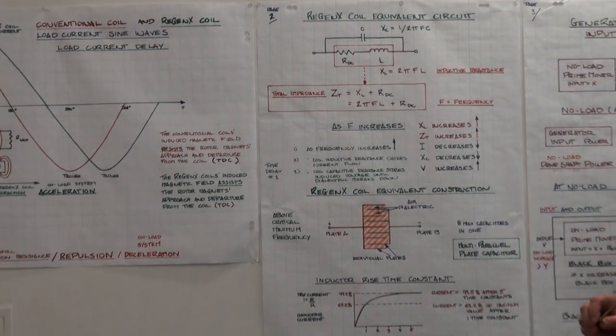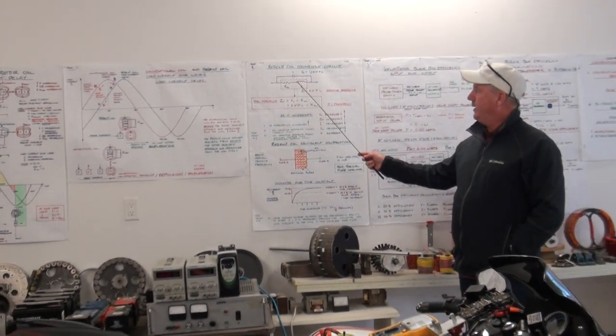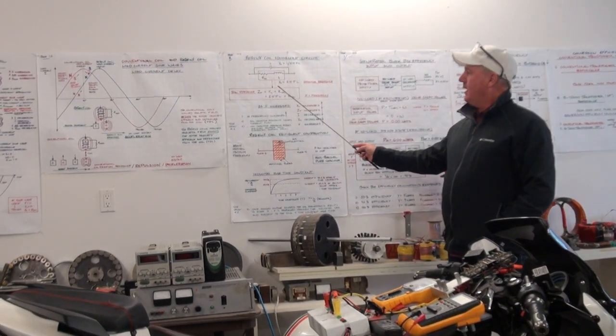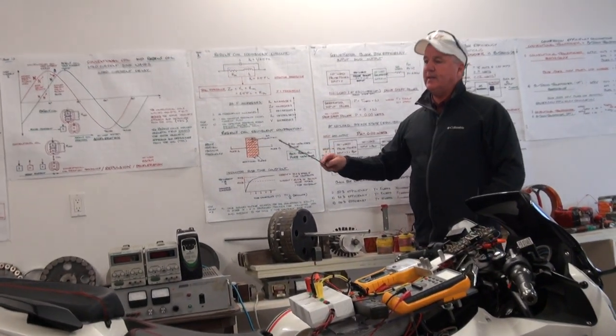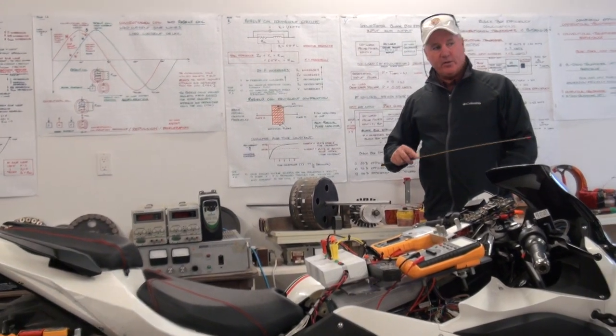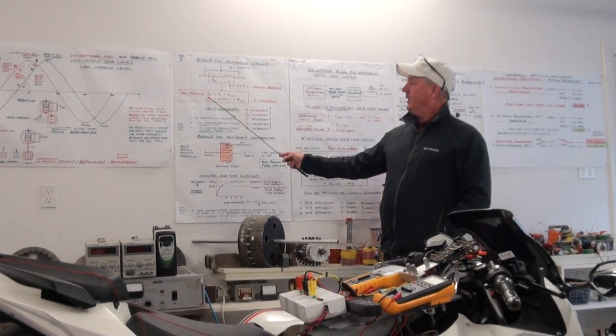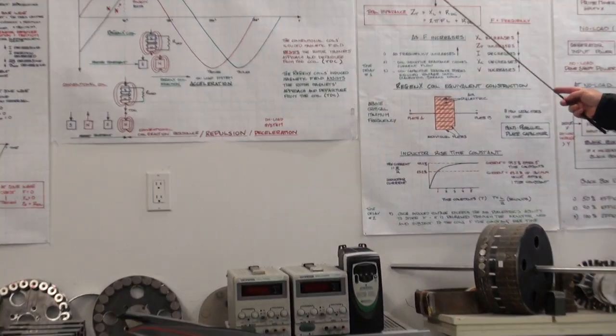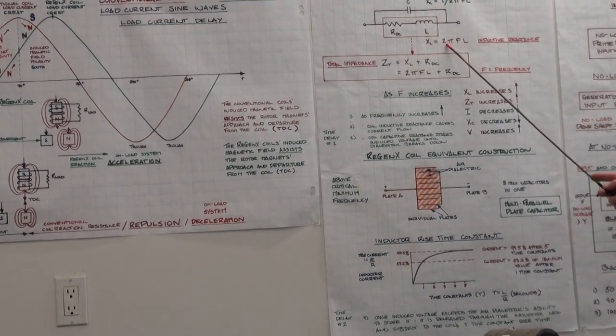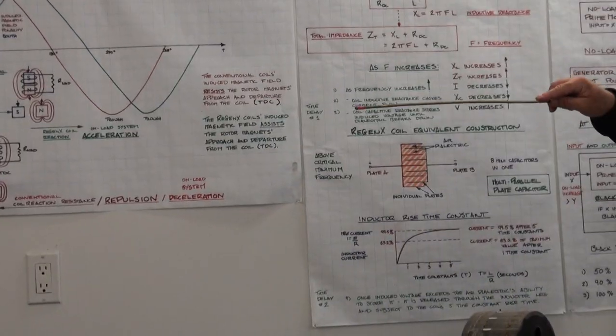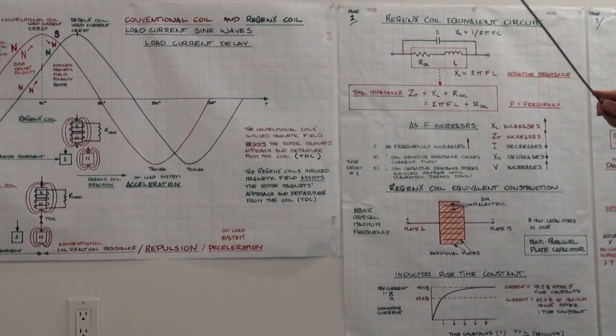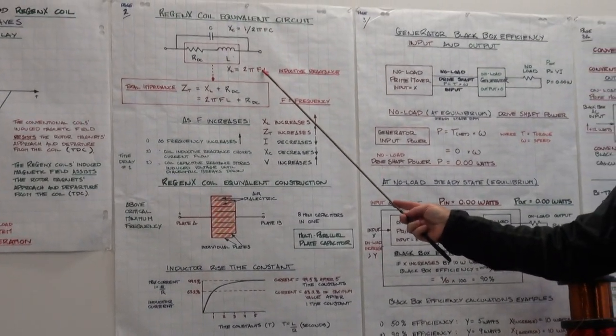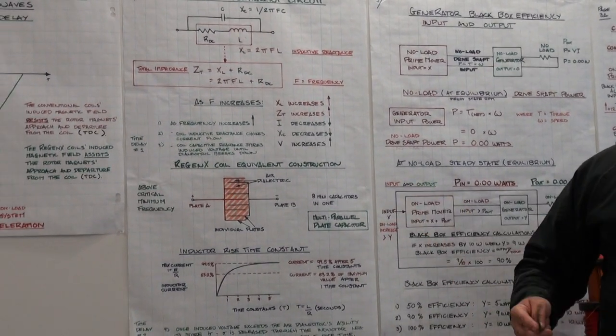In a normal generator coil, the capacitance is negligible. The total impedance — that's the AC resistance to current flow — ZT is the inductive reactance plus the DC resistance. The inductive reactance of the coil is 2πFL. So what you saw when we were operating at a higher and lower frequency, the only parameter we were changing was the frequency of operation, thus changing the inductive reactance of the coil.